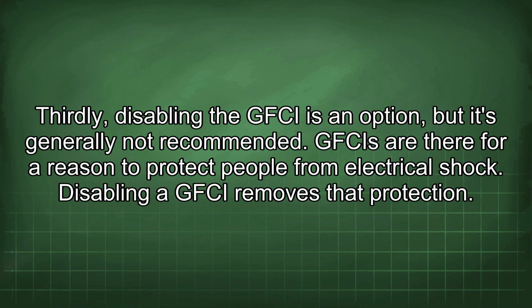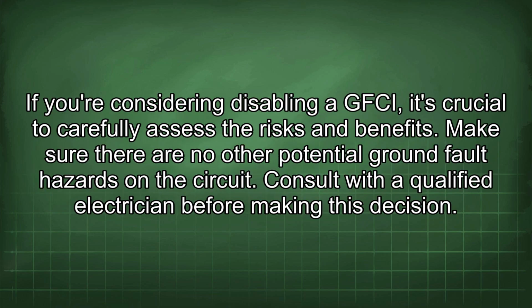Thirdly, disabling the GFCI is an option, but it's generally not recommended. GFCIs are there for a reason, to protect people from electrical shock. Disabling a GFCI removes that protection. If you're considering disabling a GFCI, it's crucial to carefully assess the risks and benefits. Make sure there are no other potential ground fault hazards on the circuit. Consult with a qualified electrician before making this decision.